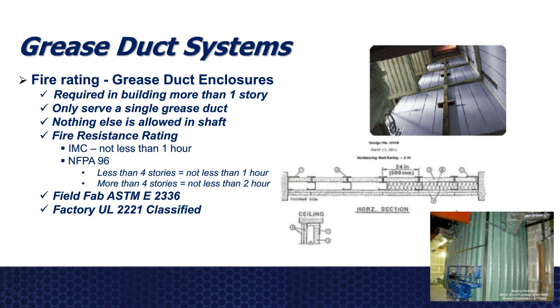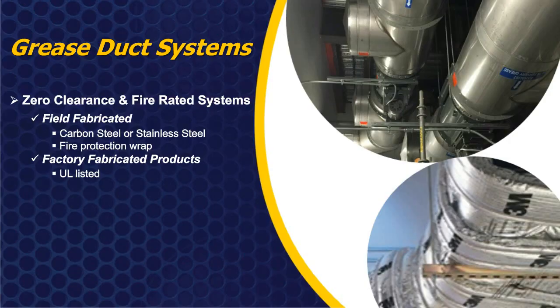So for this presentation, since we're talking about fire rating, I'm really going to focus on design and construction and factory-built products that would look at zero clearance and fire-rated systems that we could utilize in a multi-story healthcare building or an apartment or condo type building. So field product would be constructed of carbon steel or stainless steel. A fire protection wrap of certain application would need to be done for fire rating and zero clearance, and/or factory fabricated products with the UL listing.